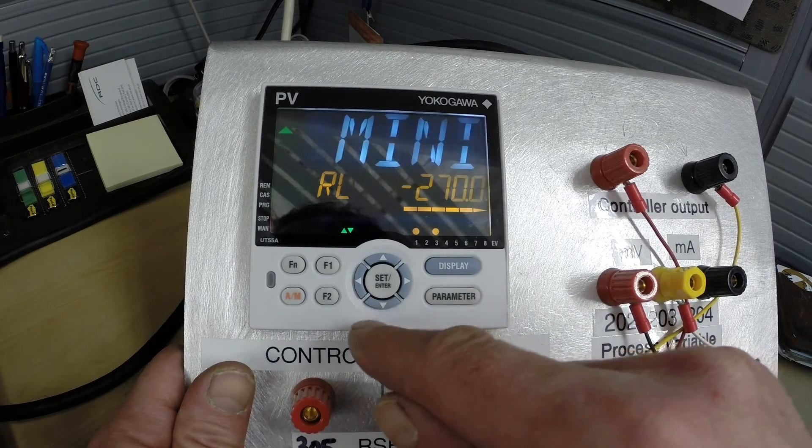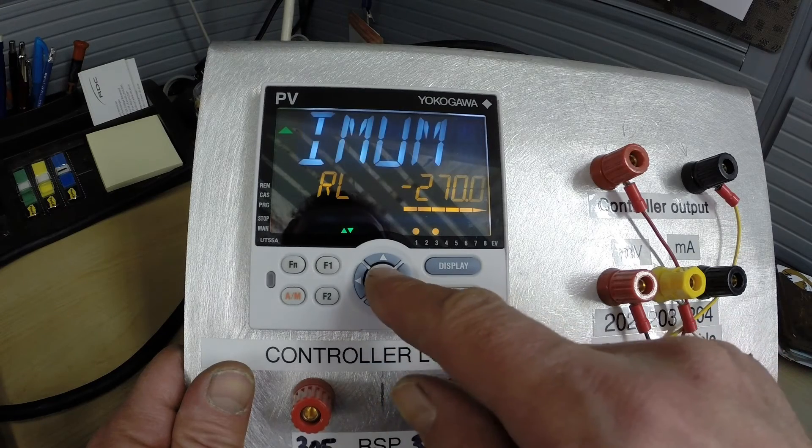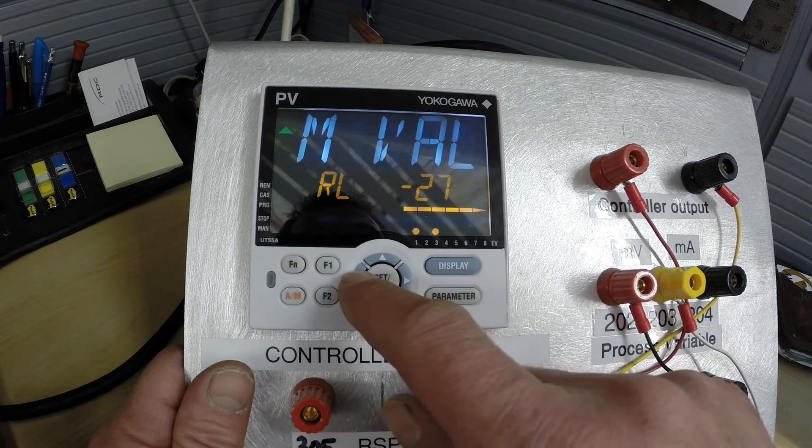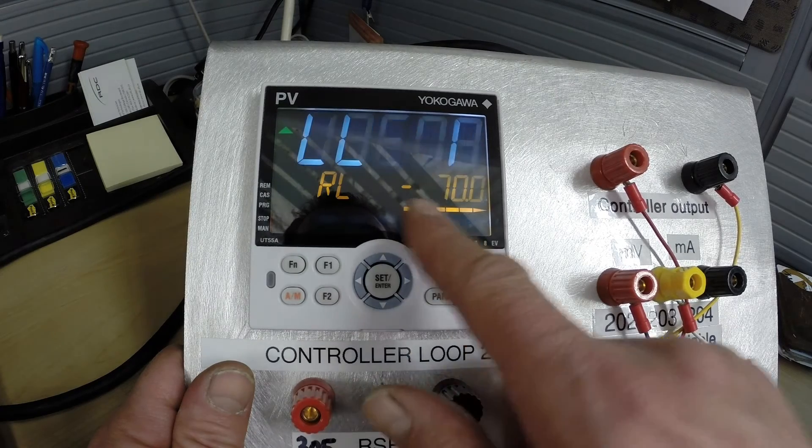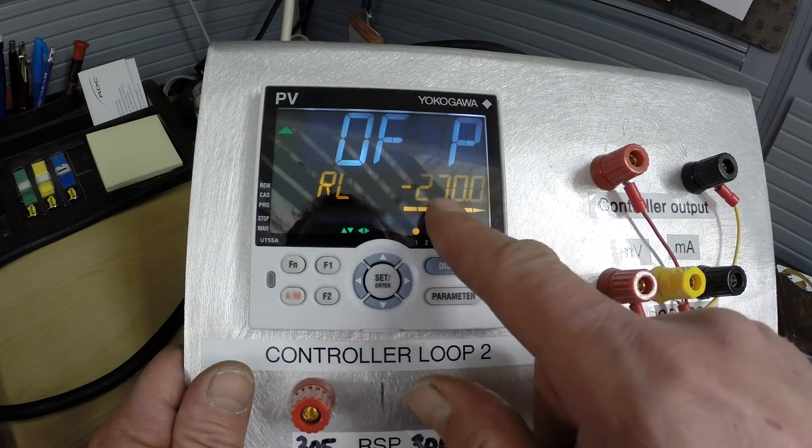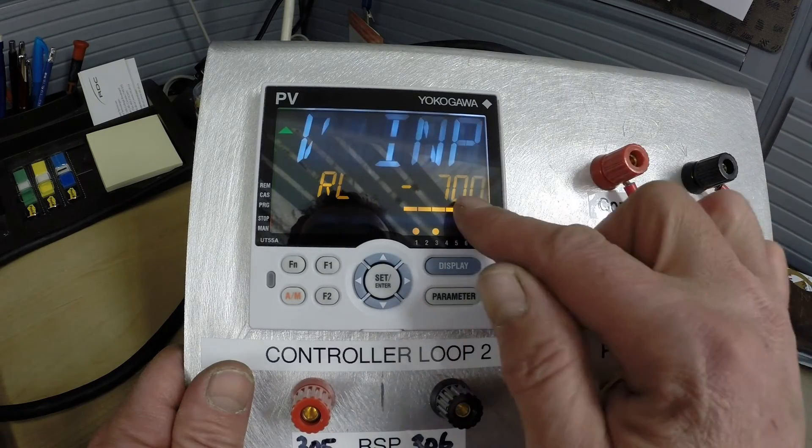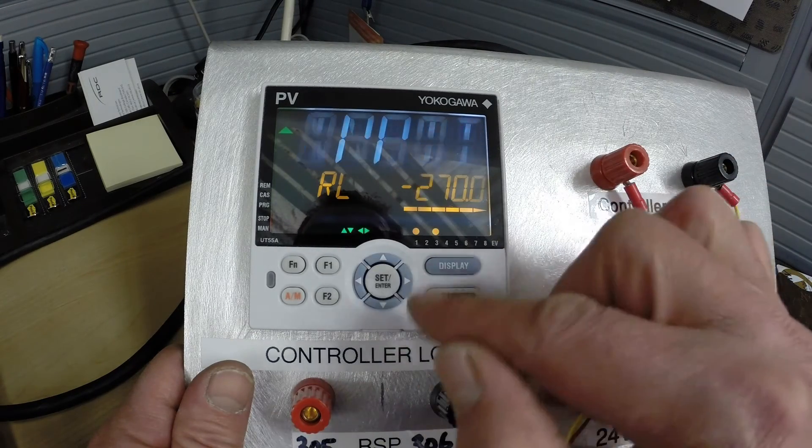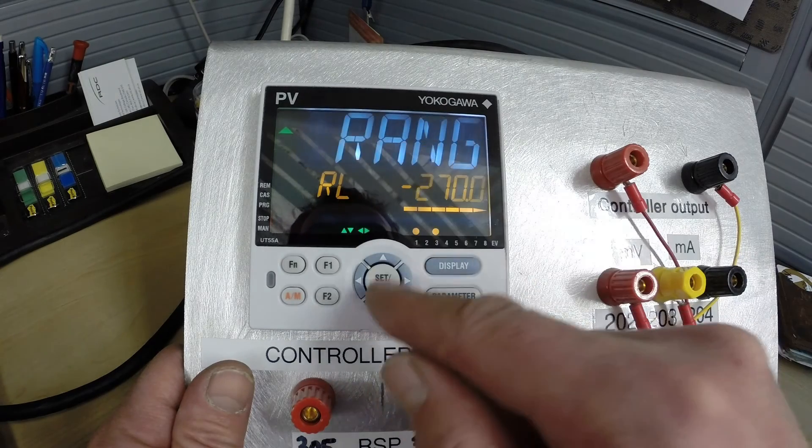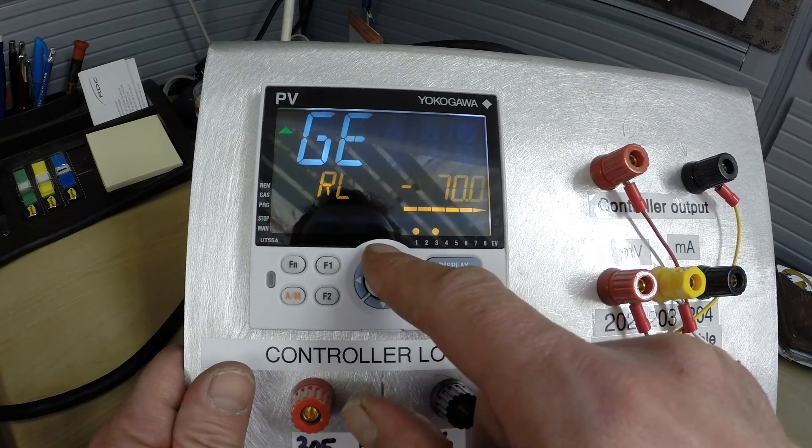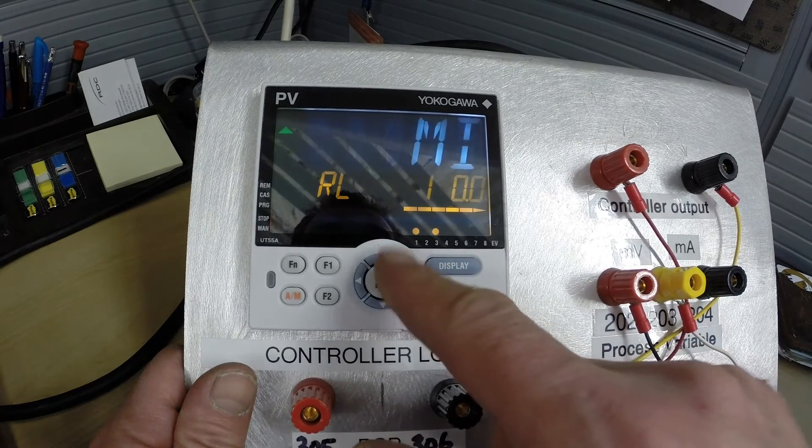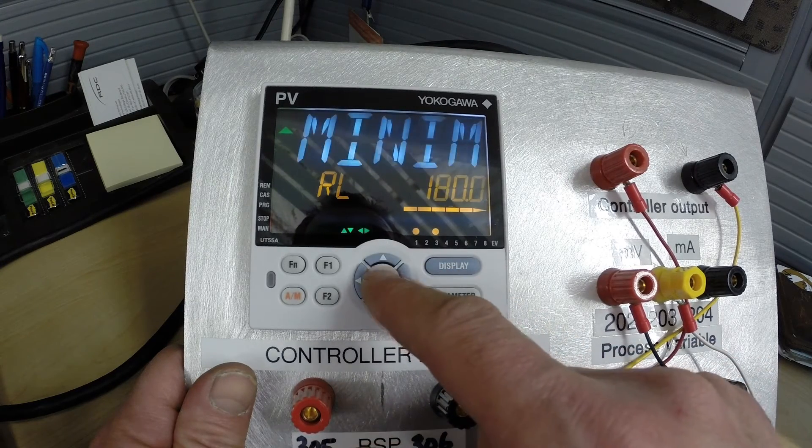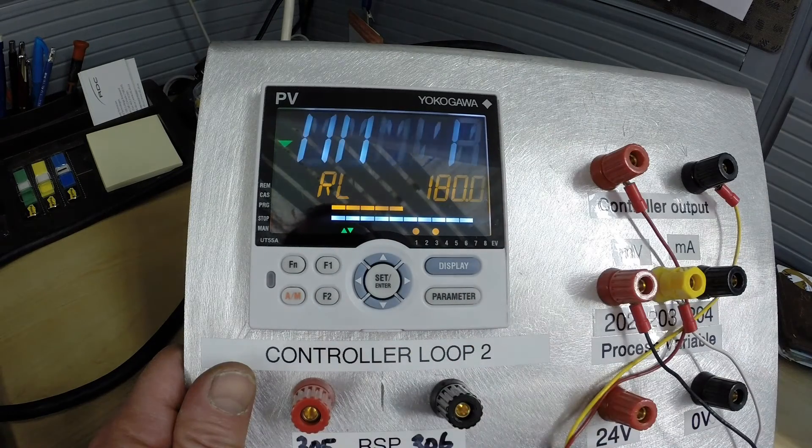Go down to our range low which in this case we're going to set for 180 degrees. So let's go in there and change that to 180 degrees. Depending on which decimal location you go to it will scroll through faster or slower. If you go over to the 100th position you can change it right away. We are now positive 180 degrees for range low set and we're going to call that good.